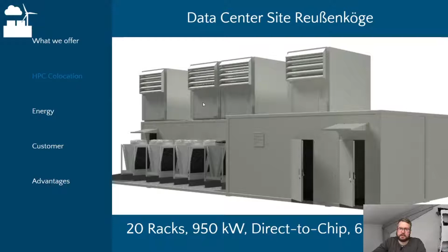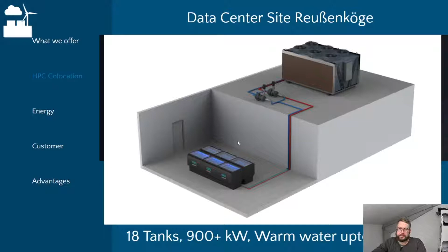And the immersion module, which we haven't fully designed yet but will look similar. I just wanted to show you how those tanks look. They're connected at a very high temperature level with a fairly simple redundant pump, moving to a cooling solution. You basically never need to create artificial cooling, because they can run at a relatively high temperature level.